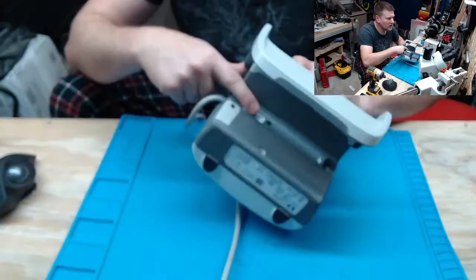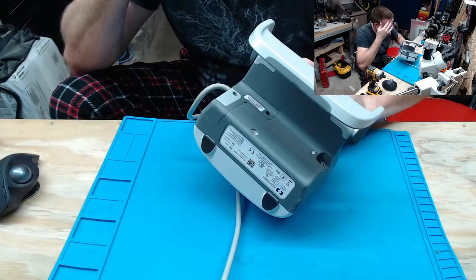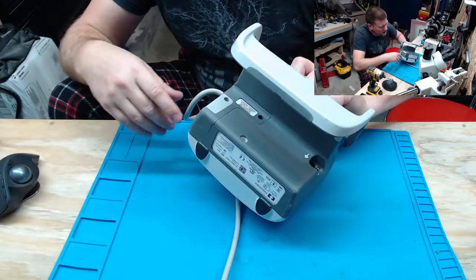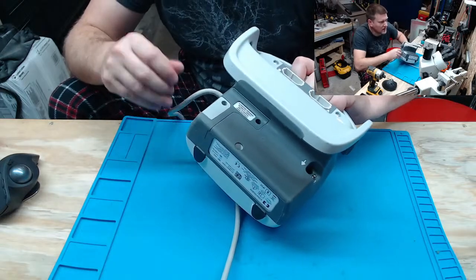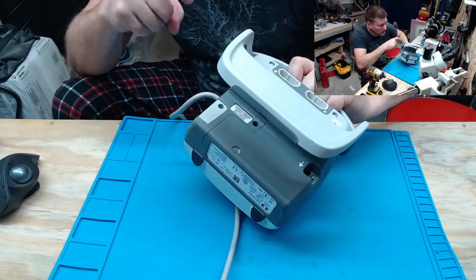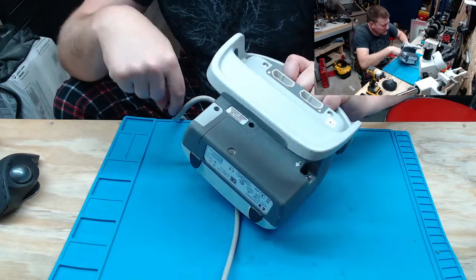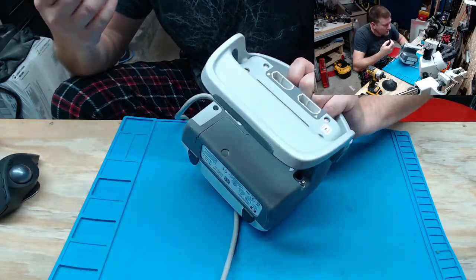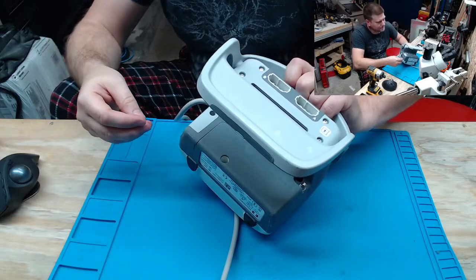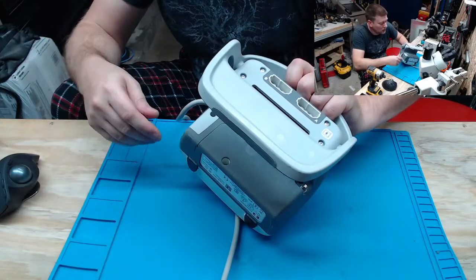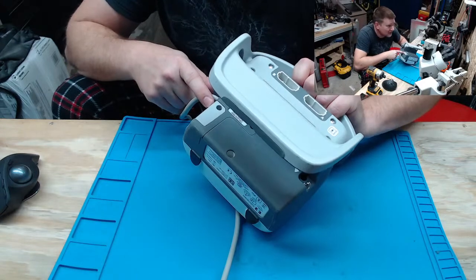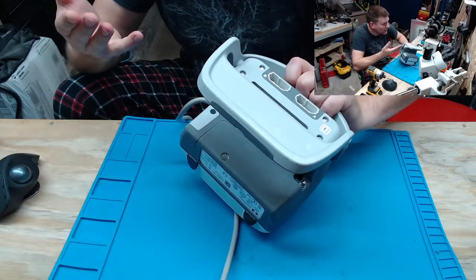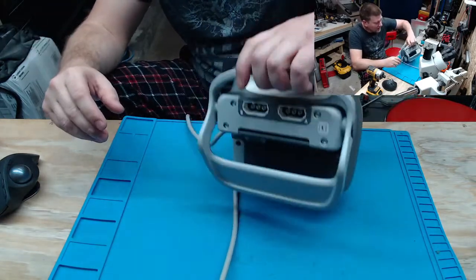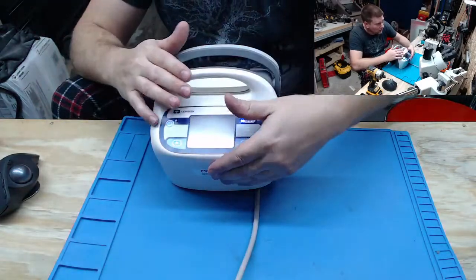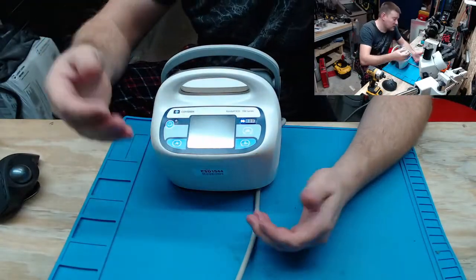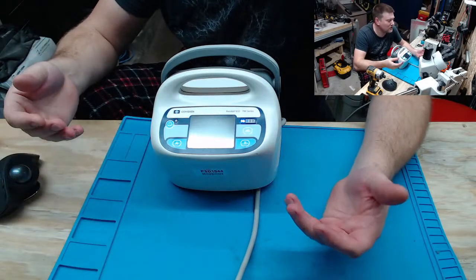This little cover right here has 2 screws that hold it on. And the thing is, it's got a 90-degree IEC cord plug, and it plugs straight into the body. But the problem is you can't access it unless you're a Biomed. So if it starts coming unplugged in here, which does happen quite often, then you're going to get error codes, no charging, won't power on, errors like that. Just because they had to put a cover with 2 screws.